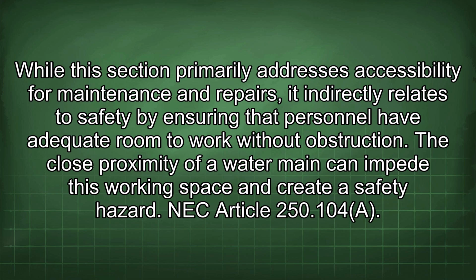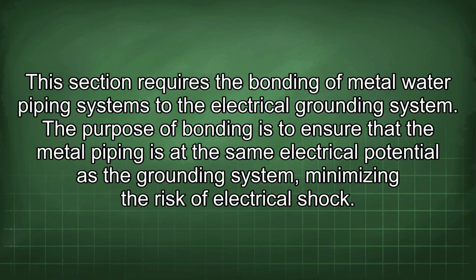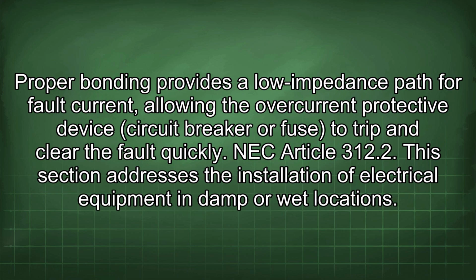NEC Article 250.104(A). This section requires the bonding of metal water piping systems to the electrical grounding system. The purpose of bonding is to ensure that the metal piping is at the same electrical potential as the grounding system, minimizing the risk of electrical shock. Proper bonding provides a low impedance path for fault current, allowing the overcurrent protective device, circuit breaker or fuse, to trip and clear the fault quickly.